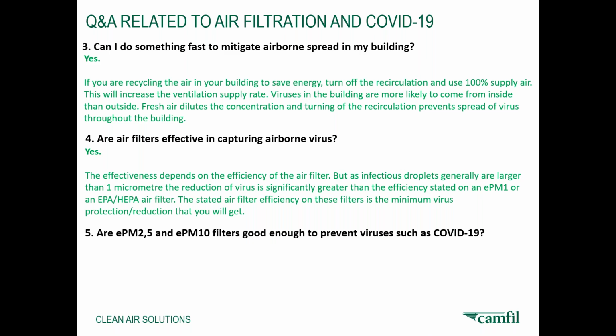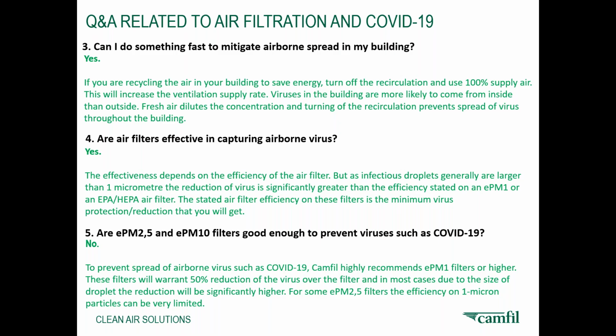Are EPM 2.5 and EPM 10 filters good enough to prevent viruses such as COVID-19? Definitely no, these cannot prevent the COVID virus. To prevent spread of airborne viruses such as COVID-19, Camfil highly recommends EPM 1 filters, because these range from 0.3 to 1 micron or higher category. These filters will warrant a 50% reduction of the virus over the filter in most cases, and due to droplet size reduction, the effect will be significantly higher.